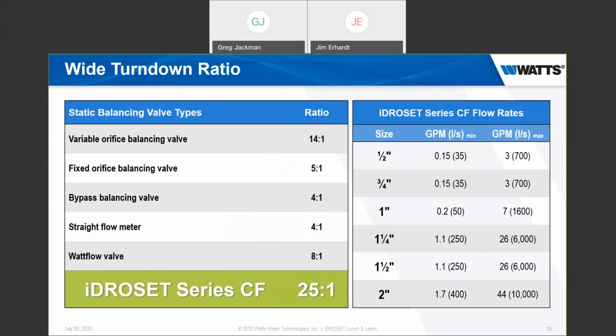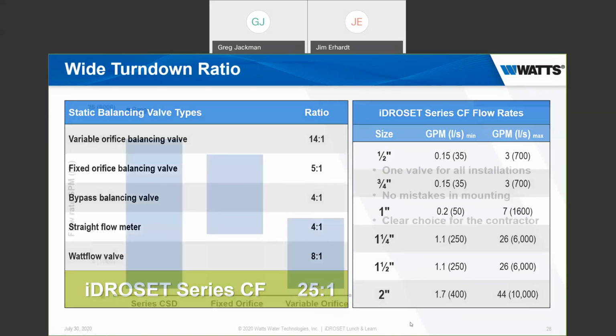The 1 inch goes from 2,000 to 70,000 BTUs. And you can see the range for the large valves. We go all the way up to, actually, 440,000 BTUs on the top end on the 2-inch valve, 17,000 to 440,000, which is pretty impressive. On the left side, we can see the ratio. Variable orifice is typically 14:1. Fixed is usually 5:1. The iDROSET is 25:1. So we have a significantly wider operating window.